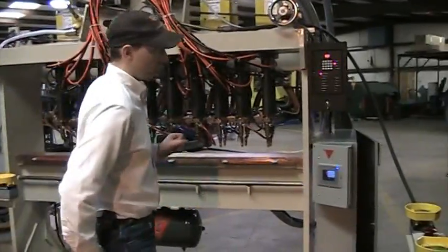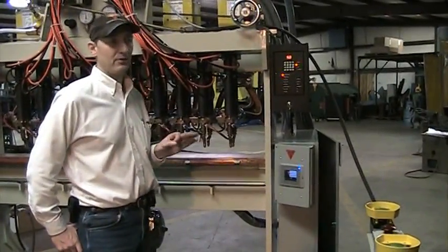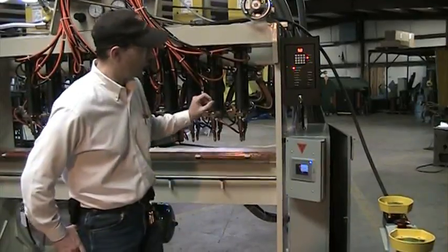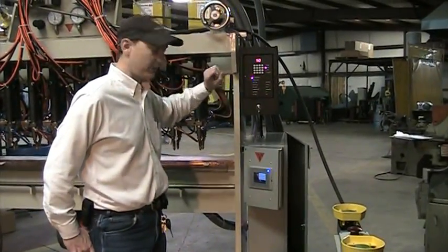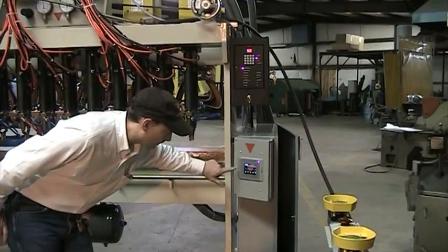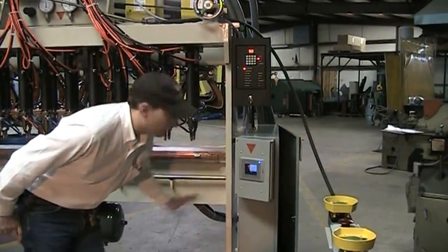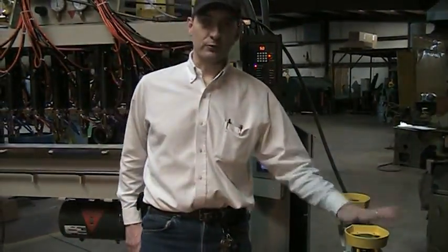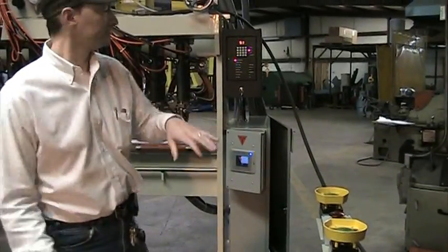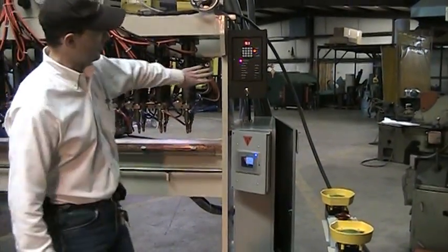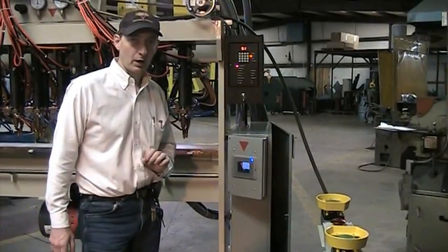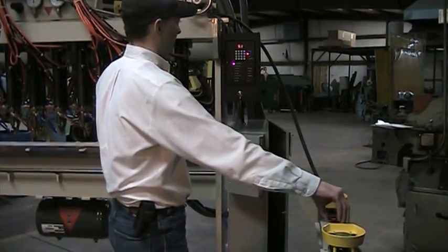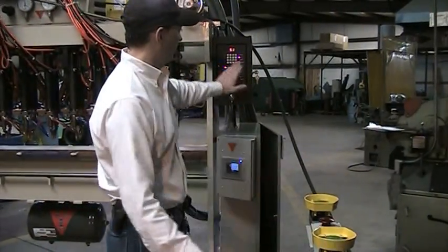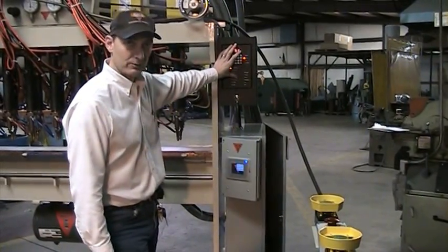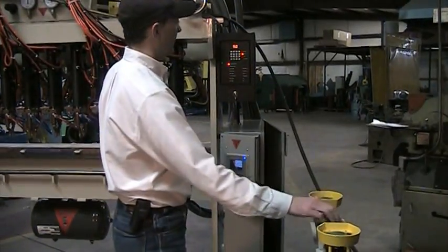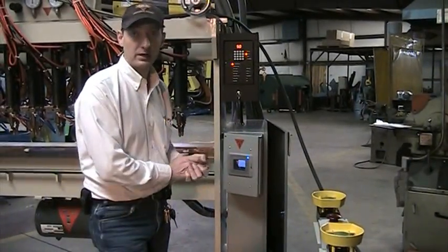Also, we wanted to show you one error condition that can be fairly common. So what I'm going to do, we're sitting on program 50. I've turned on my 5th transformer, so everything should be ready to go. And what I'm going to do is hit E-stop, for some reason, because I didn't like the way something was looking. And you notice the control automatically switched to 51. If I then pull it up and start to go, my control is off 1 sequence from where it should be. I can strike E-stop again and it'll go back to 50 and we're ready to run.